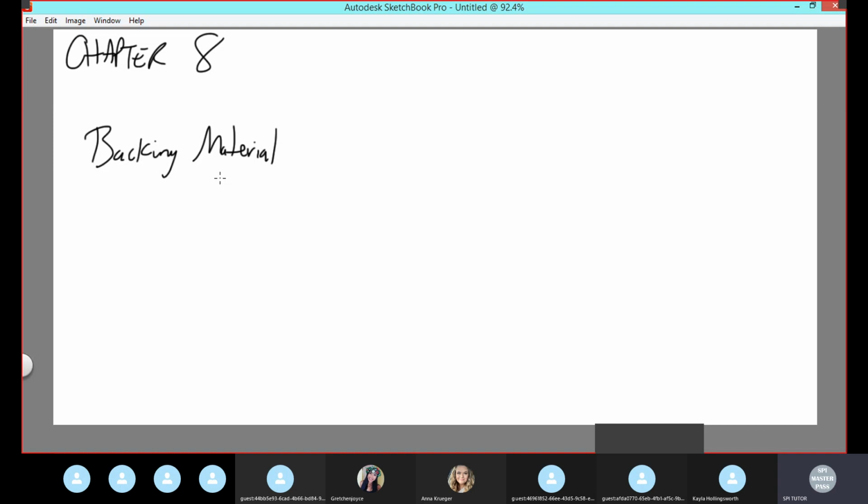This is just a definition sort of deal. You don't have to go into depth. Just know what a backing material is, and the three little consequences of having a backing material, and your questions will really just fall under that. So you have a PZT element, and right behind it, you have the backing material.